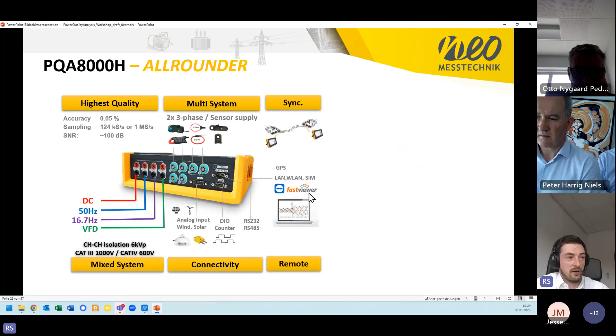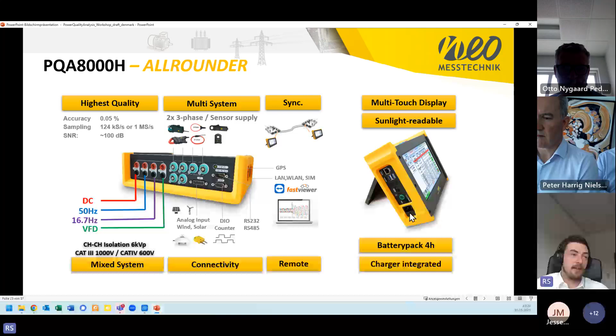And we have also power supply. So we have unipolar and bipolar power supply for AC/DC current clamps, or flux gate transducers can also be used. And we have additional inputs like analog inputs, wind, solar input, digital inputs, counter, or RS-232 or 485 inputs. Synchronization can be done via GPS. We have also the possibility for easy remote connection via UMTS or via standard LAN or Wi-Fi connection. So this is also possible. Fast viewer, TeamViewer, this is everything installed. And multi-touch display, sunlight readable. We have the battery pack, and the charger is integrated, so you directly go with your cable to this instrument or device, and therefore you don't have this external charger.